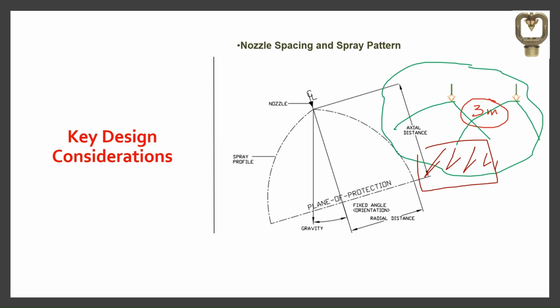And in some cases, as per NFPA 15, we can exceed the requirements above 3 meters distance. However, we need to check with the manufacturer about these particular details. And also, a single system shall not protect more than one fire area. And you can see the figure of a nozzle spray pattern here on your screen. This is the nozzle. This is the spray pattern. This one we call it as spray profile. And we have a fixed angle orientation, radial distance, axial distance. All these will be discussed in detail when we cover the topic of water spray nozzles.